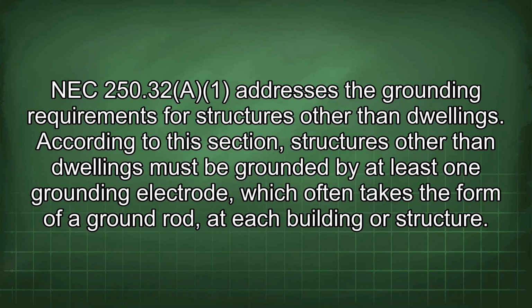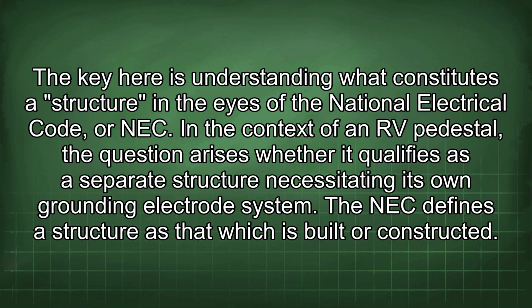NEC 250.32 addresses the grounding requirements for structures other than dwellings. According to this section, structures other than dwellings must be grounded by at least one grounding electrode, which often takes the form of a ground rod, at each building or structure. The key here is understanding what constitutes a structure in the eyes of the National Electrical Code, or NEC.